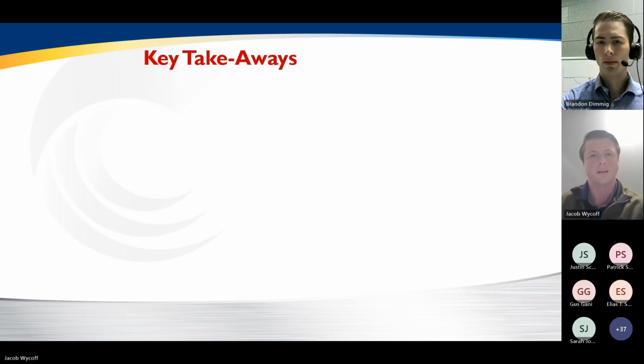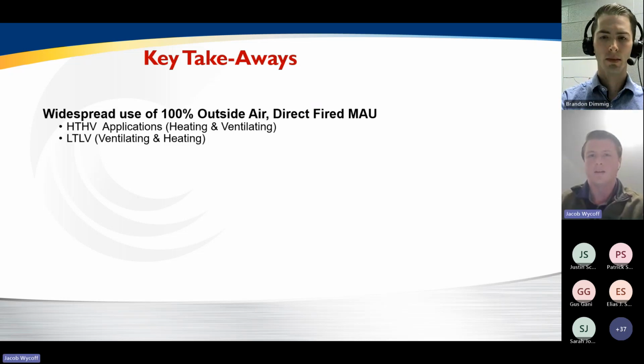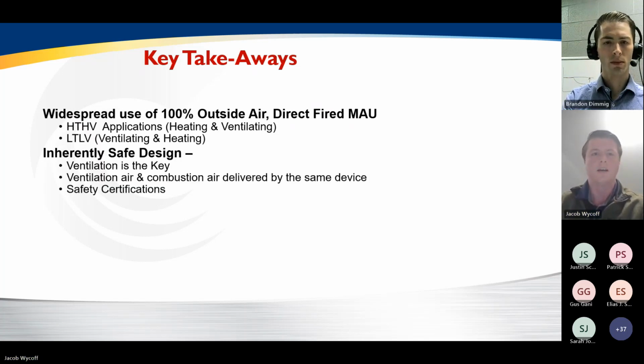So some of the key takeaways we want you to come away from this presentation with: 100% outside air direct fired makeup air units are not niche in the industry. They're very widespread, used in many different applications, both HTHV and LTLV. The inherently safe design that Brandon talked about: ventilation is going to be the key for this. With 100% outside air, ventilation air and combustion air cannot be separated. You're not going to be able to get combustion without also ventilating the space. And safety certifications require certain limits on products of combustion and certain control safety features. Overall, you're not compromising safety by going with this. You're providing an inherently safe design that poses no danger to any occupant.